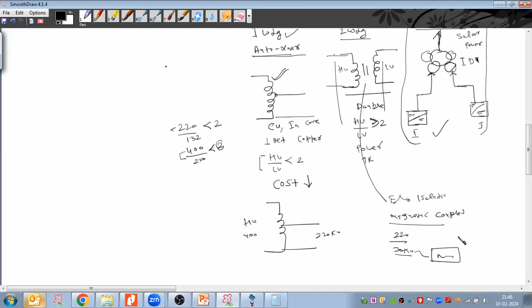But whenever I'm working on grid substations, on the 400 kV side or the 220 kV side, there is no industrial connection. This is all grid connections. Grid connections means the chance of harmonics is very less, and working on extra high voltage, I have a choice that instead of going with the two winding, I can go with the one winding. I'm taking tappings from the windings only. So it means my 400 kV and 220 kV are electrically connected.